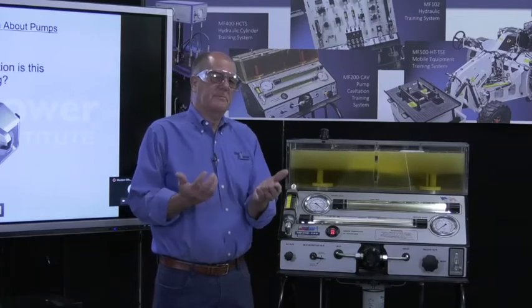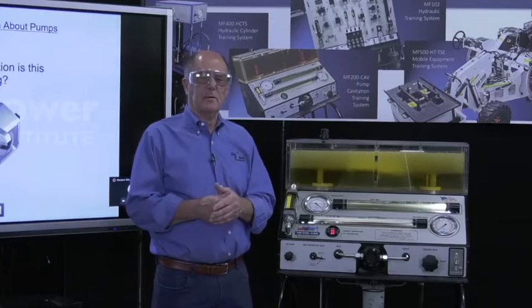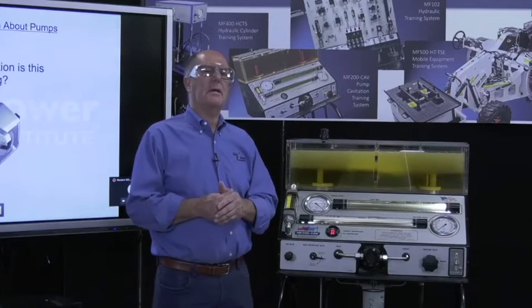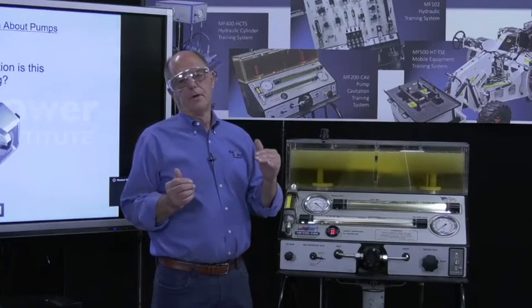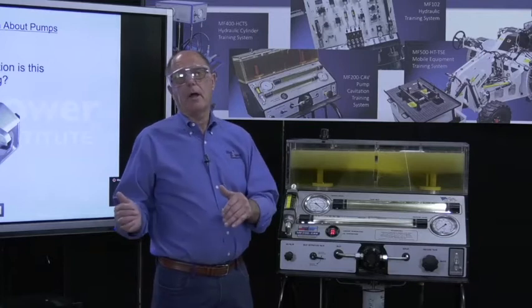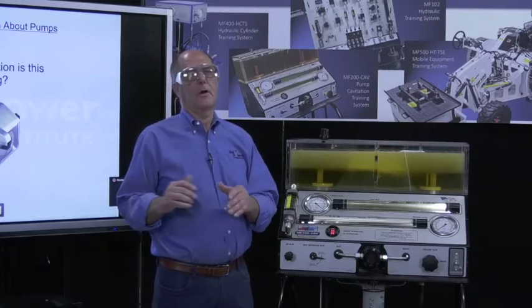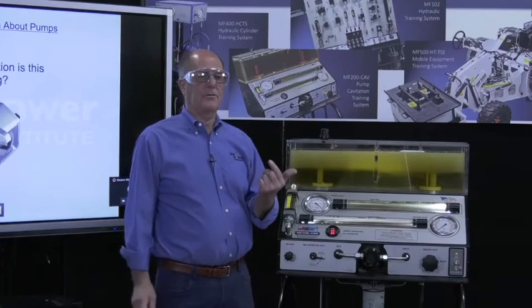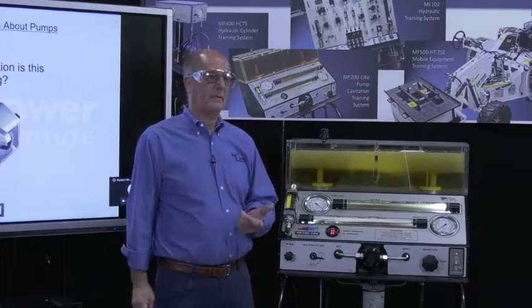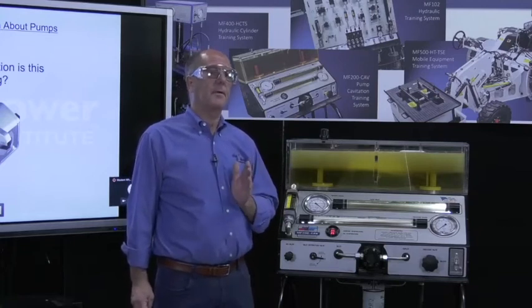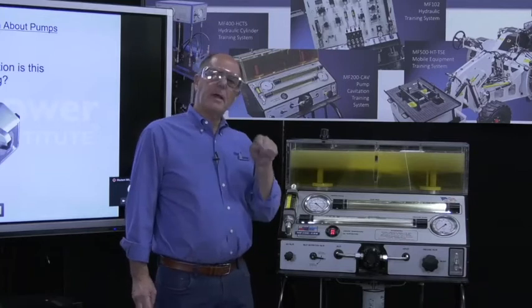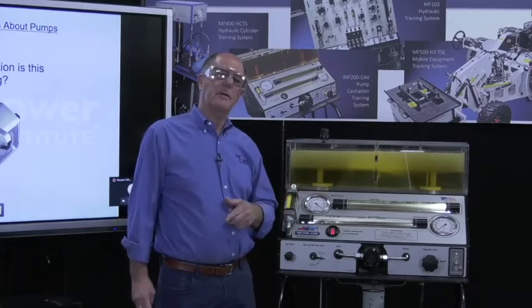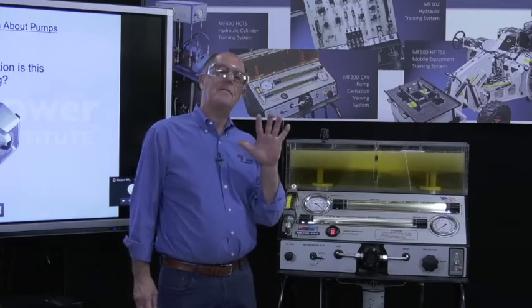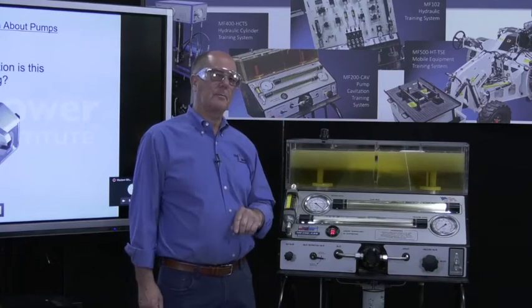So let's just ask this hypothetical question. How many pumps have been replaced over the years because I had a low flow rate, but it wasn't because the pump was fine. It was because there was a problem on the intake side of the pump, which I never monitored in a pump flow test. So all of the elements that affect flow output should be monitored on a pump flow test, meaning we need 5 pieces of diagnostic equipment on board.